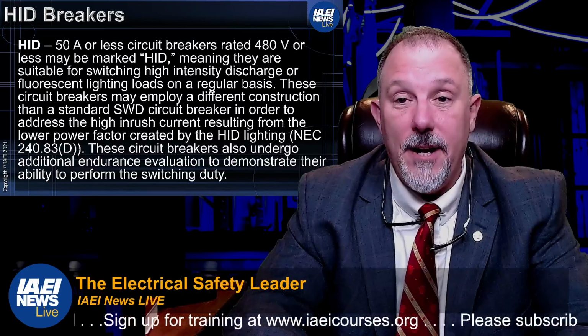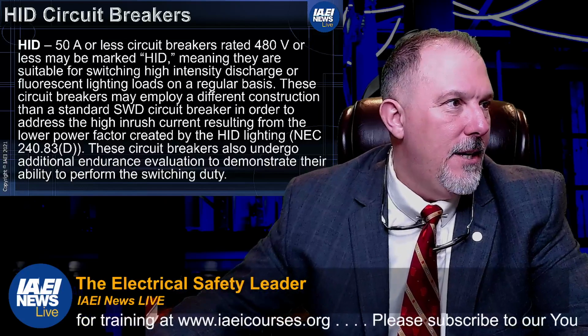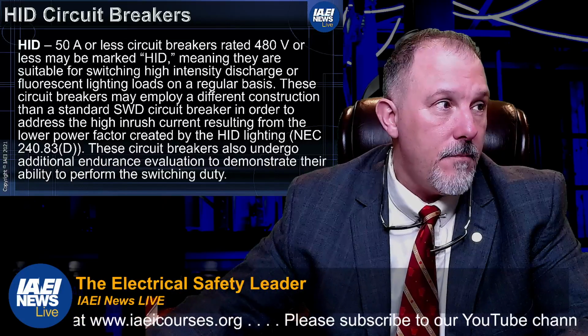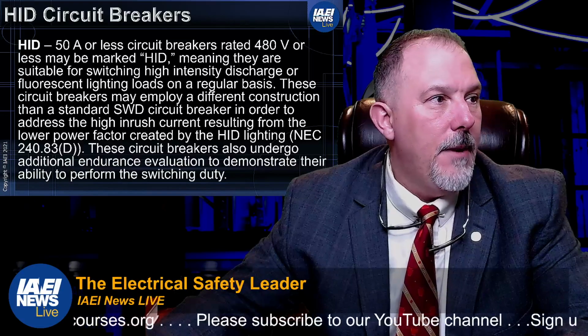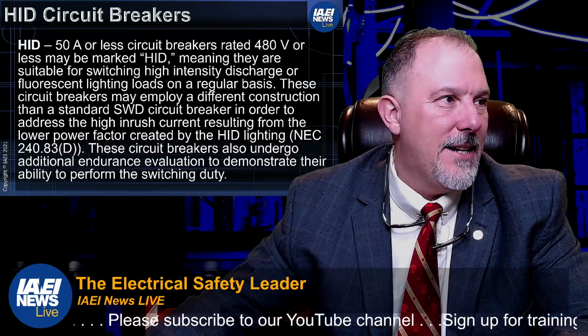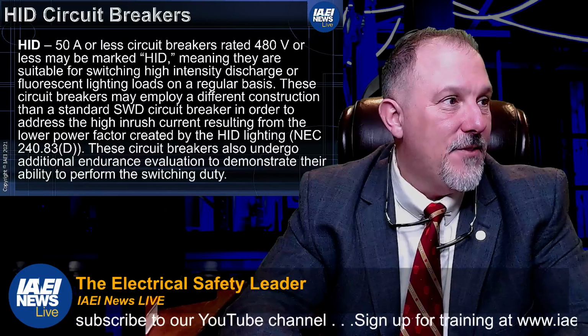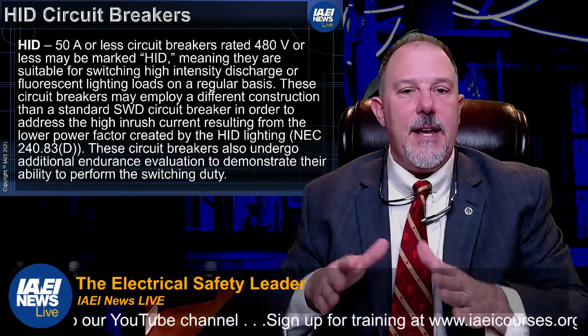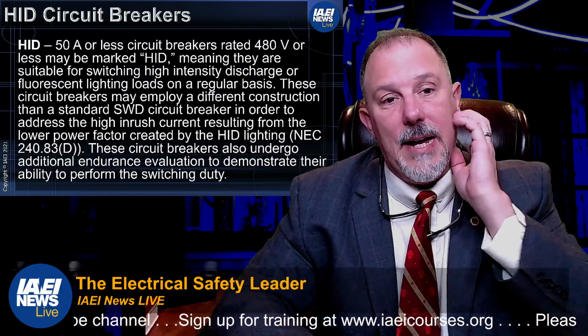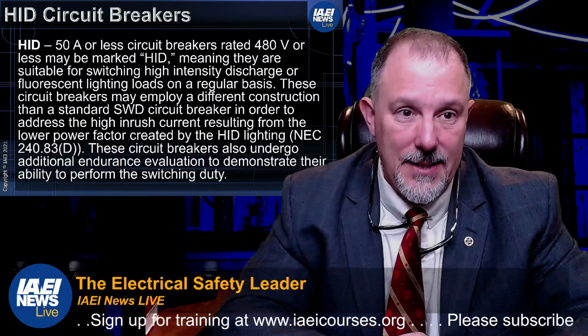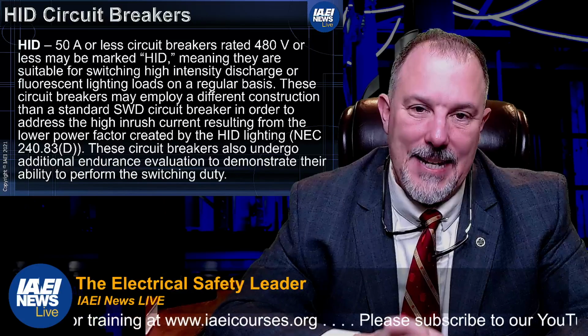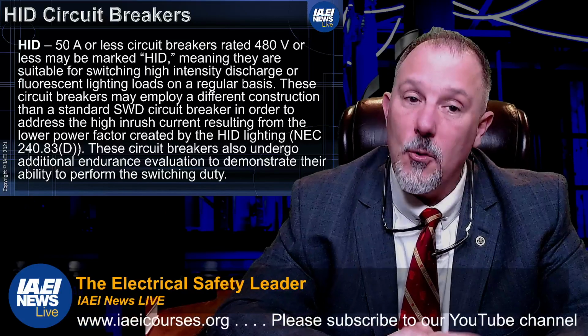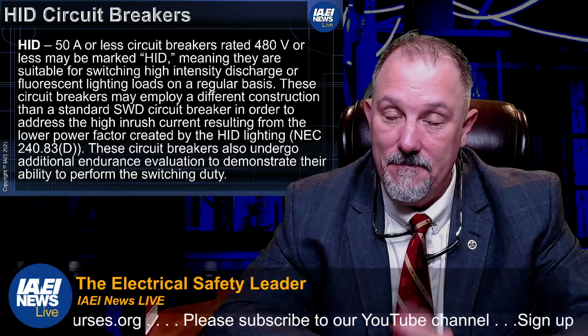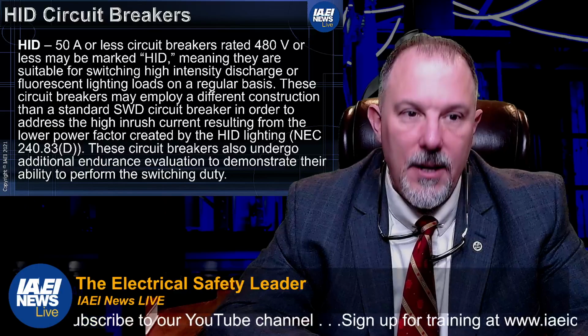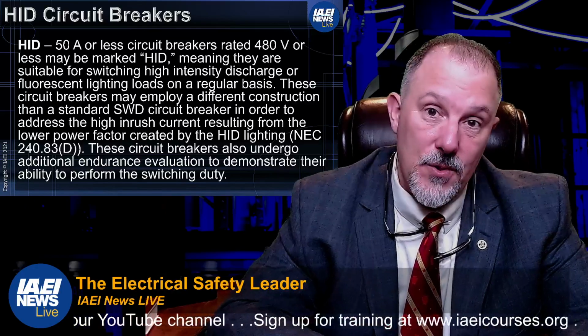Watch. Ready? Circuit breakers. HID circuit breakers. So, HID circuit breakers, and I'm fixing it as I go because I just have to. HID circuit breakers, 50 amps or less, circuit breakers rated 480 volts or less can be marked HID. And what it means is that they're suitable for switching high intensity discharge or fluorescent lighting loads. Did you know you needed a special breaker if you had fluorescent loads?